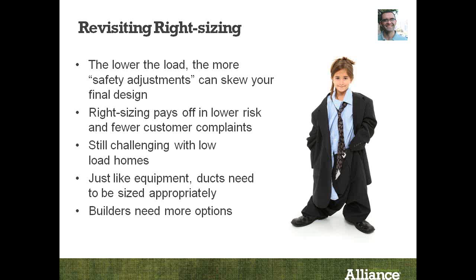So revisiting the right sizing again, lower load means the safety adjustments can skew your final result more. And I think if we think about this from the perspective of when you had a 5-ton air conditioning system in a house, it didn't really matter what your electronic appliances were because they were a minor part of 5 tons. Now if you're at a 1.5-ton cooling load and you install a lot of electronics in your house, like very large plasma screen TVs, you're going to add around 1,000 BTUH to a house that's already pretty low load. So you don't have as much margin or as much, what would you call that? Margin of error. Safety factor. Safety factor. Yeah, so the right sizing pays off with lower risk and fewer customer complaints, but your safety margin is now smaller too.